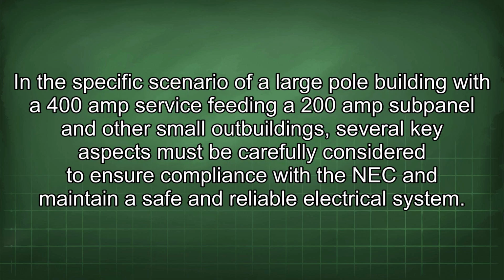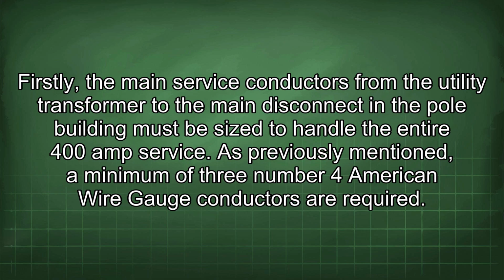In the specific scenario of a large pole building with a 400 amp service feeding a 200 amp subpanel and other smaller buildings, several key aspects must be carefully considered to ensure compliance with the NEC and maintain a safe and reliable electrical system. Firstly, the main service conductors from the utility transformer to the main disconnect in a pole building must be sized to handle the entire 400 amp service. As previously mentioned, a minimum of 3 number 4 American wire gauge conductors are required.